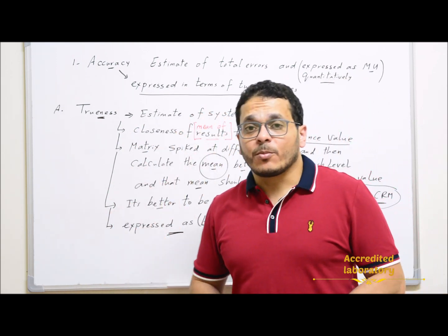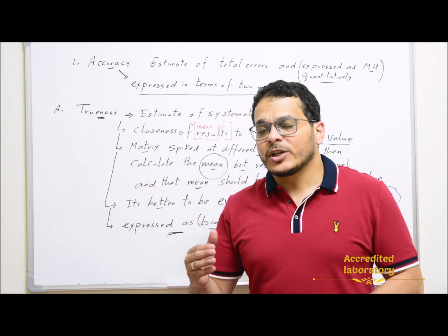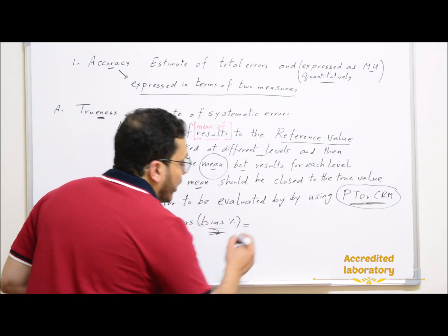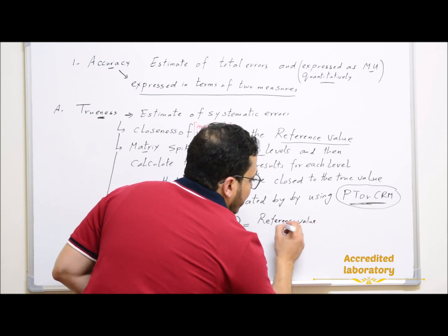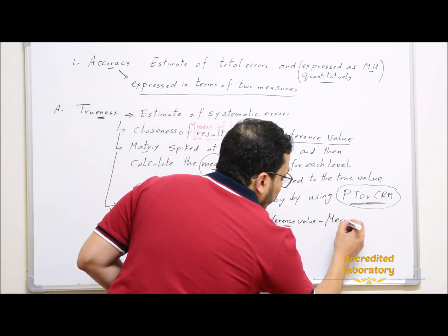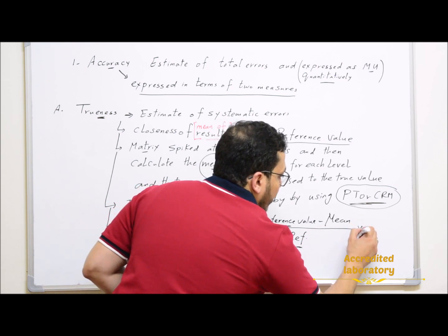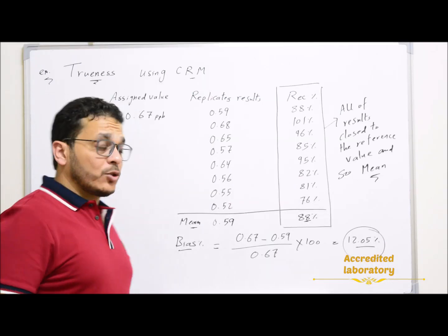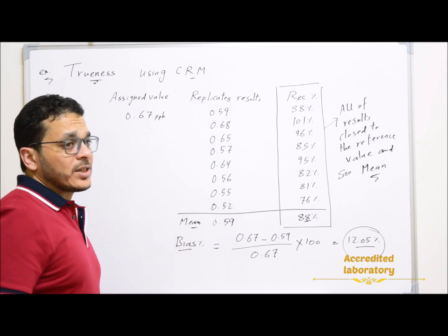To evaluate trueness, you make 6 to 10 replicates from your CRM, calculate the mean of all replicates, and then calculate the bias. Trueness is expressed as bias percentage, which equals: (reference value − mean of replicates) ÷ reference value × 100. Here is an example of how to evaluate trueness and calculate bias using certified reference material.